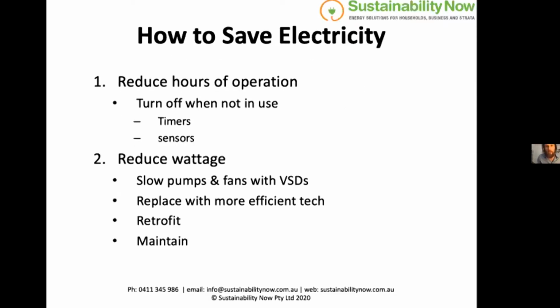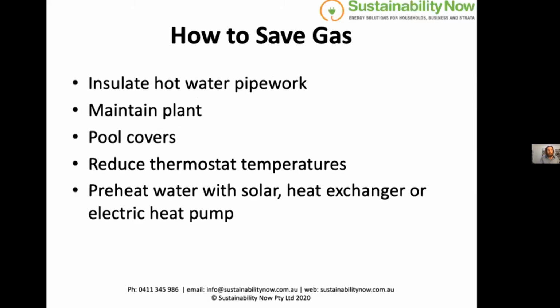So how do we save electricity? There are two key ways. One, we can reduce the hours of operation, so turn things off when we're not using them, and we can use timers and sensors to do that in their simplest form. Or two, reduce the power consumption of the device. Your consumption charge, kilowatt hours, is a factor of watts and time. So we can turn it off, or we can reduce its wattage. Again, as I mentioned before, slowing pumps and fans down with variable speed drives, replacing older technology with more efficient, or retrofitting what you've got, and maintaining. That's an important one: making sure that your maintenance schedule is up to date for all of these items of plant.